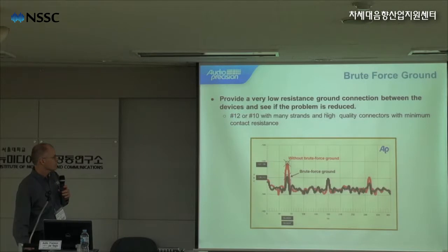So the brute force ground, this shows an example of a signal measured in the frequency domain without grounding and with grounding. So in this case, a number 12 or number 10 heavy gauge wire with many strands and high quality is connected between the device under test and the ground. You can see how we have a signal at about 60 hertz here. This would be the line frequency, and it's dropped significantly with the brute force ground in level.